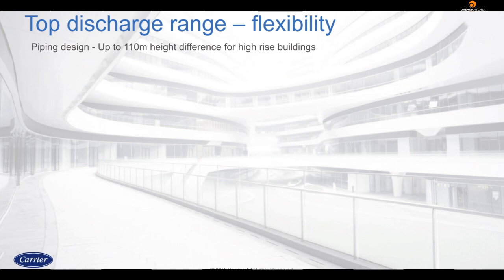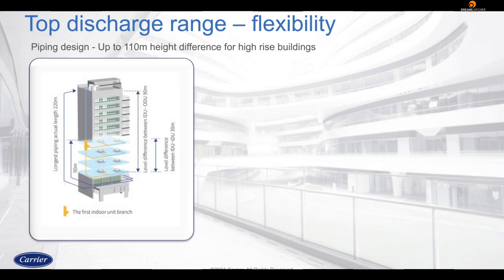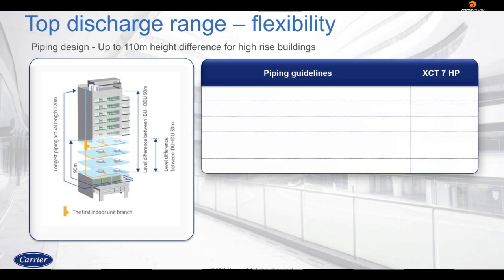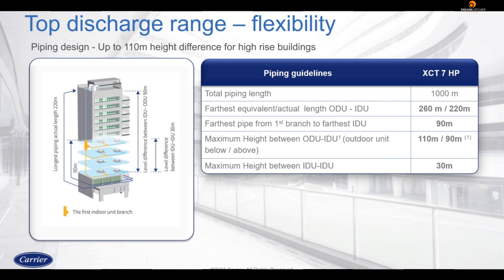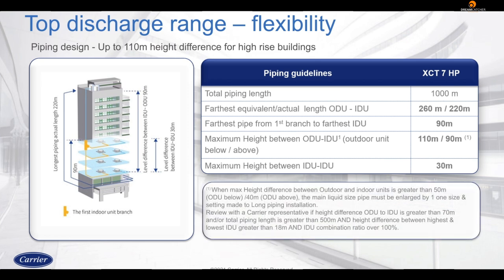The XCT7 also offers amazing flexibility in terms of its design. The piping system is not just at par with industry standards, but it also surpasses it by offering piping lengths of up to 1 kilometer with amazing flexibility in terms of the placements of the ODU and IDU. It can accommodate a 110-meter height difference when the outdoor unit is placed at the top of the building and 90 meters if it is placed at the bottom of the building, thus making it ideal for high-rise buildings.